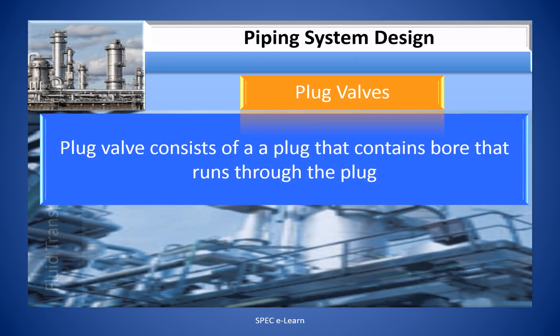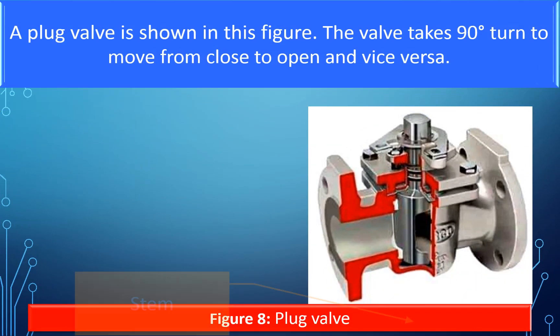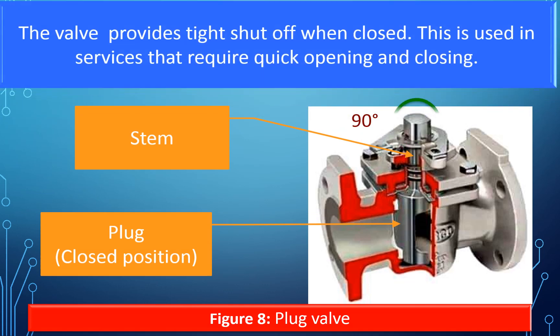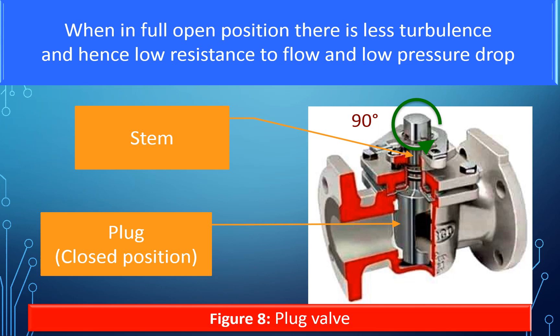The plug valve consists of a plug that contains a bore running through it. The bore is conical or cylindrical, and the bore size is the same as the pipe diameter, hence it allows full flow. The valve takes a 90-degree turn to move from closed to open and vice versa. It provides tight shut-off when closed and is used in services that require quick opening and closing. When in the full open position, there is less turbulence, resulting in low resistance to flow and low pressure drop.